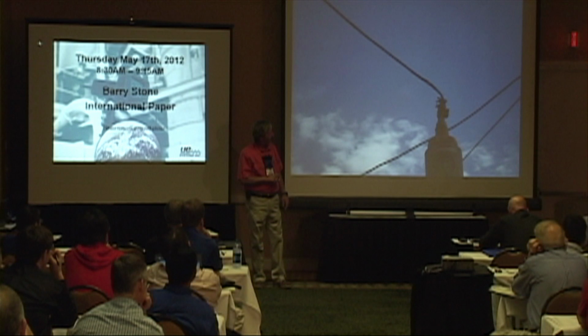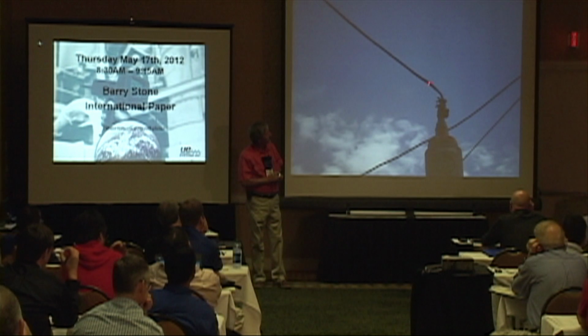I go up here with my Ultra Probe, my UE 10,000. When you walk into this substation, the noise is, I'm not going to say it's unreal, but it's extremely loud. Even with my sensitivity set low, you can still hear things. This is one of the insulators up on top of the transformer. Can y'all see that? Right there.